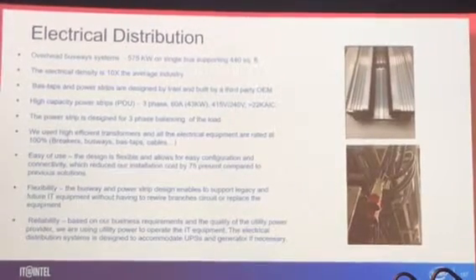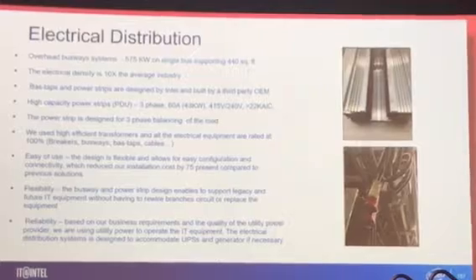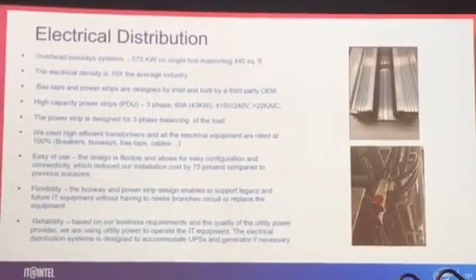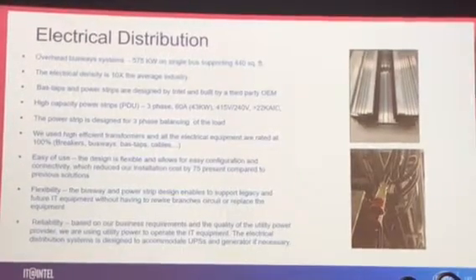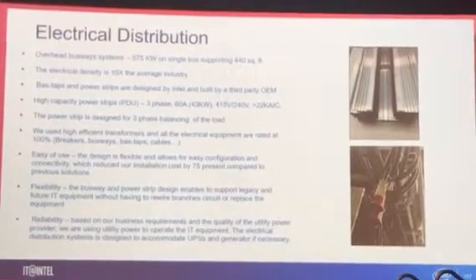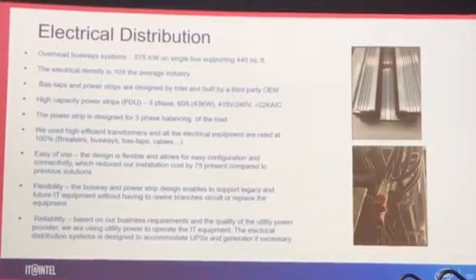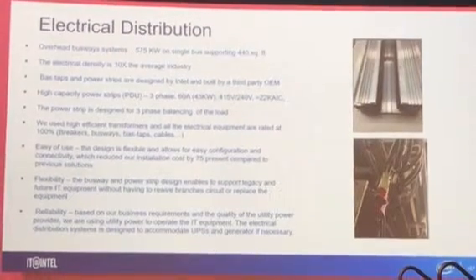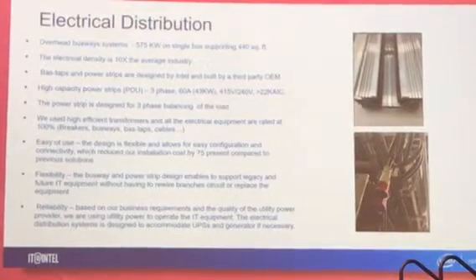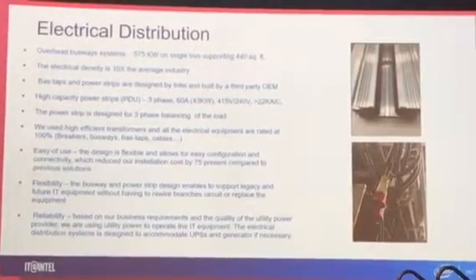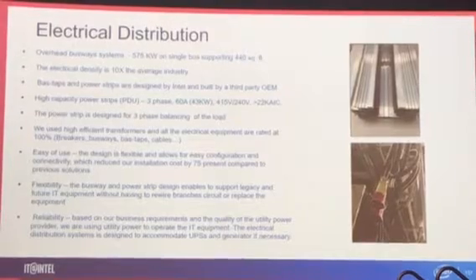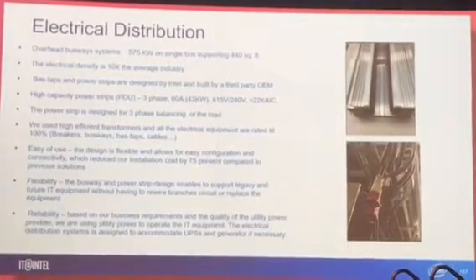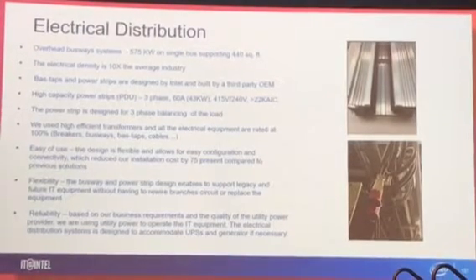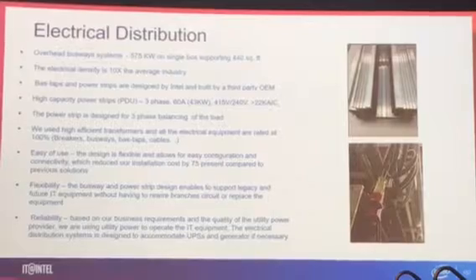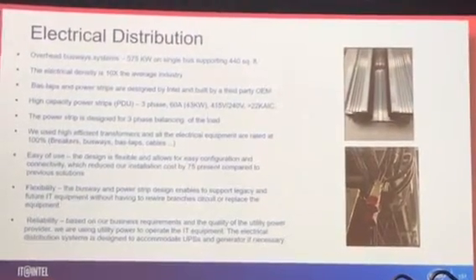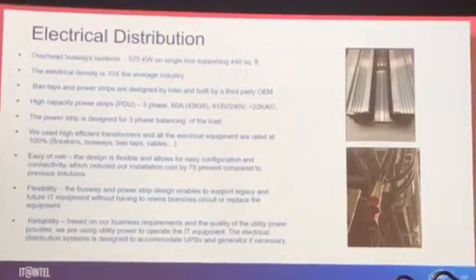Like I said, for the electrical distribution we're using 800 amp busways. Each busway is 575 kilowatt. Because of the high density, and remember, those are 20-inch racks, it's 10 times greater than the average industry. Those are custom-made busways, bus taps, PDUs to meet our demand, 43 kilowatt per rack. The PDUs, like I mentioned, 415, we had to use high short circuit current PDUs, because we bring in power right from the transformer, the short circuit is high, so we needed to use high-rated equipment with the short circuit.